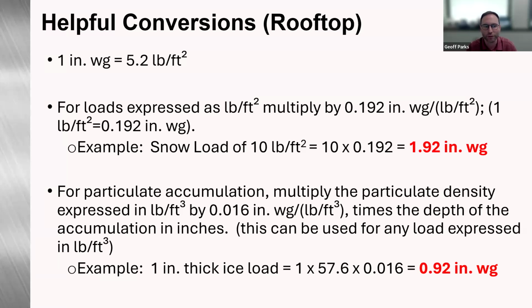But what we can do is, for loads that are expressed in pounds per square foot, you can multiply that by 0.192 inches water gauge. So what this example here I'm showing you is, if you have a snow load of 10 pounds per square foot, you could do 10 times 0.192, and that'll equal 1.92 inches water gauge.